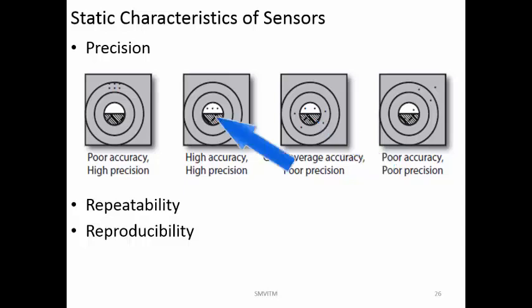If in the other case you can measure only one value, that value itself will be accurate. In that case, we can take only one value and use the correction factor so that you shift the value from where it is to very close to the actual value. But in this case, you have to compulsorily take 4 or 5 different readings and take their average. If it has poor accuracy and poor precision, then you have to simply discard that device because it is not going to give you a correct value all the time. So that is very dangerous.